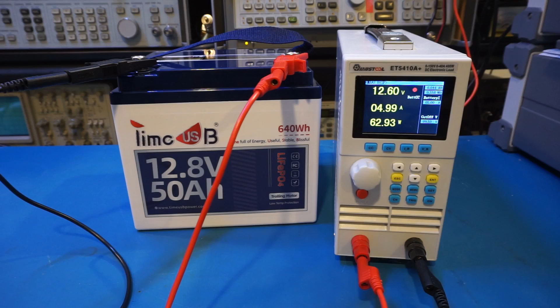Alright, the discharging test had completed. I didn't capture the exact moment of the cutoff, but as you can see here, the measured capacity is almost exactly 50 amp hours. It is a few milliamp hours under, but well within the statistical tolerance of 50 amp hours. So I would say the Timeusb battery meets its specified capacity rating, although just barely.